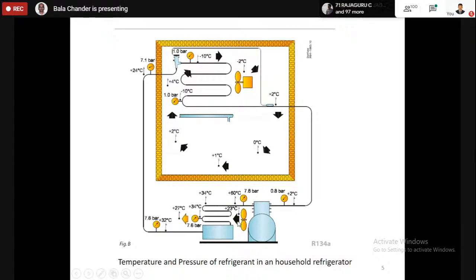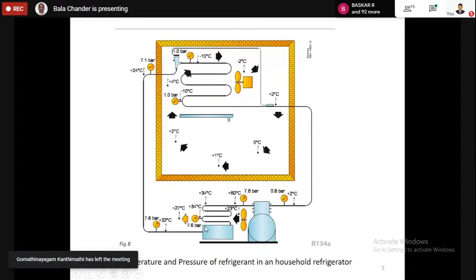Here it comes to the condenser, where it is being brought to 32 degrees centigrade, nearer to the ambient conditions. This 32 is nothing but the saturation temperature of the refrigerant, which is around 7.6 bar. At that saturation pressure, this temperature will be lying. It depends upon the refrigerant we are using. Probably if it is R134A, at 7.6 bar it is around 32 degrees centigrade. So at the outlet I am getting this, and it is moving into the expansion device.